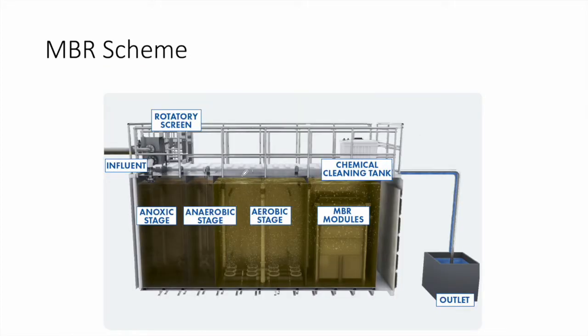This is another scheme — a packaged MBR, which is a steel container. An MBR can be pre-assembled and can be a portable, very compact wastewater treatment plant. Here, water starts by the fine screening stage, then anaerobic treatment — the anoxic stage, the anaerobic stage, then the aerobic stage with air bubble diffusers. Then we have the MBR modules, which are submerged in the water under aerobic conditions with air injection. We also have a chemical cleaning tank — these chemicals are used to clean the MBR modules.